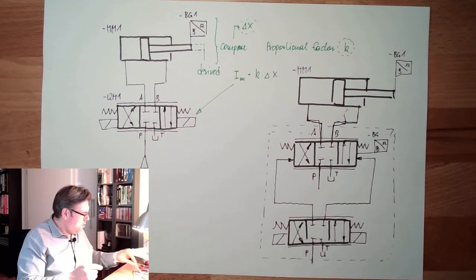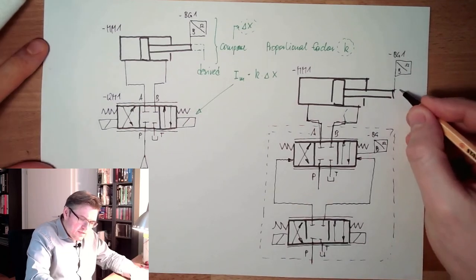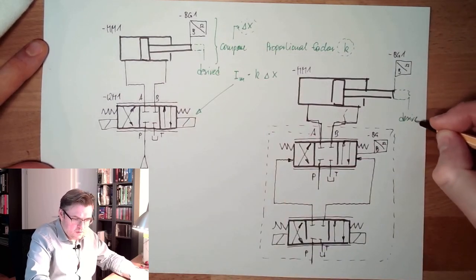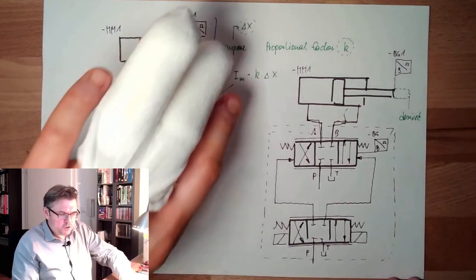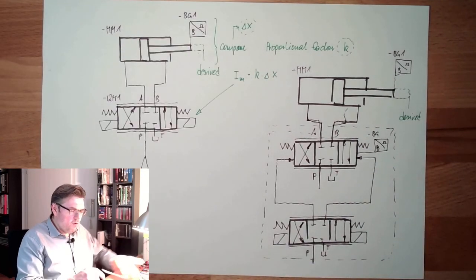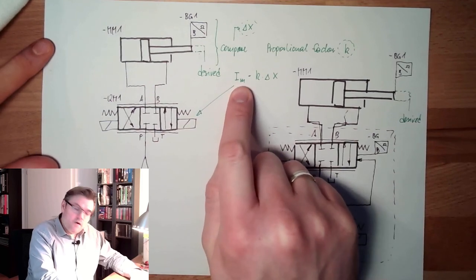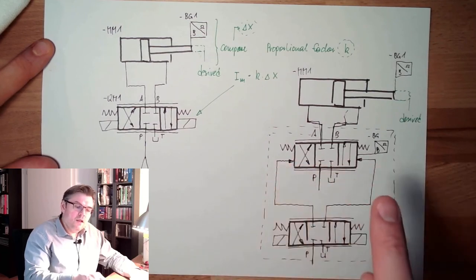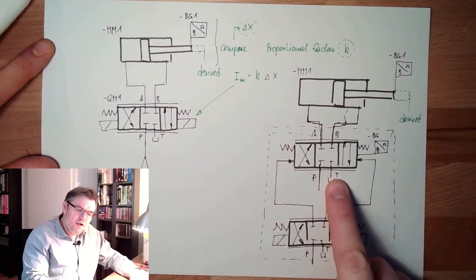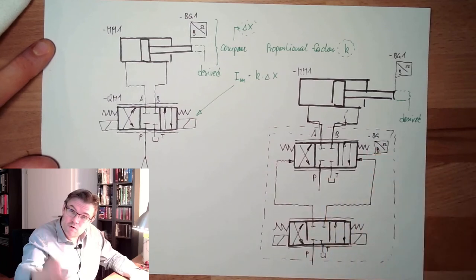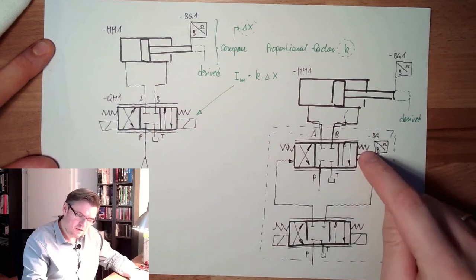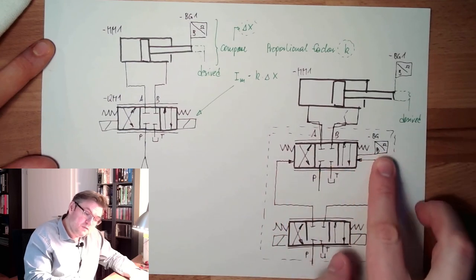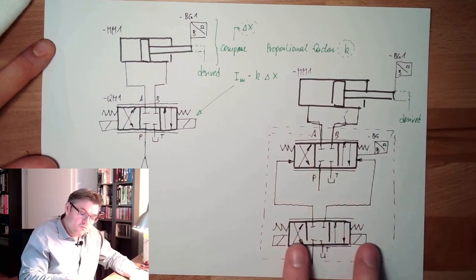So how is this working now? We do it exactly the same. We have a desired position. From the proportional factor K, we know now not the magnetizing current already, we know the position of the main control valve shall be in this direction or in this direction. Then we know a desired position of the main control valve. We know where the main control valve is currently located because we measure the position of the piston.